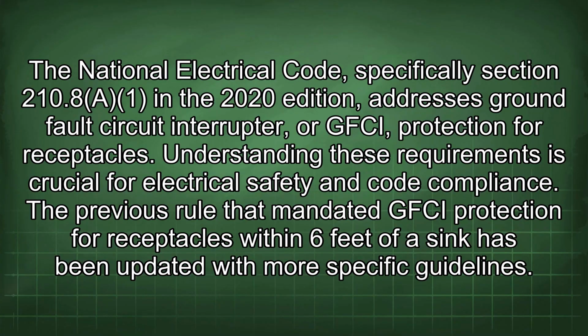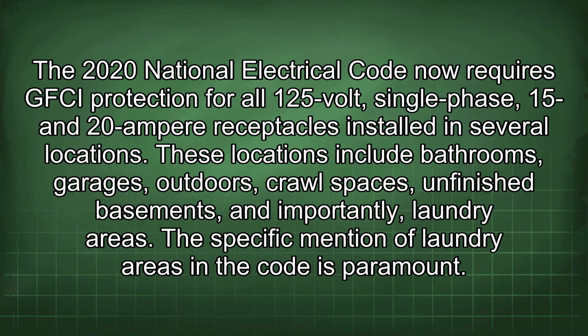The National Electrical Code, specifically Section 210.8A in the 2020 edition, addresses ground fault circuit interrupter, or GFCI, protection for receptacles. Understanding these requirements is crucial for electrical safety and code compliance. The previous rule that mandated GFCI protection for receptacles within 6 feet of a sink has been updated with more specific guidelines. The 2020 National Electrical Code now requires GFCI protection for all 125-volt single-phase, 15 and 20 ampere receptacles installed in several locations. These locations include bathrooms, garages, outdoors, crawl spaces, unfinished basements, and importantly, laundry areas. The specific mention of laundry areas in the code is paramount.